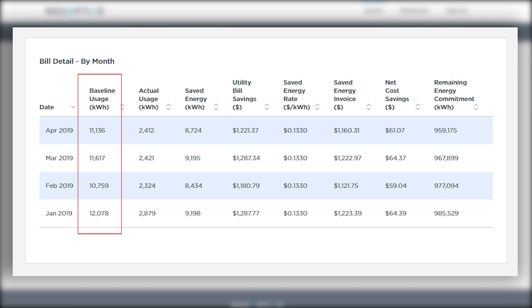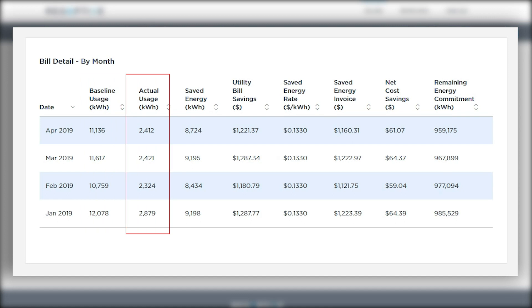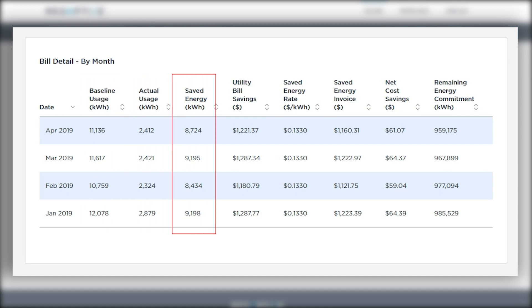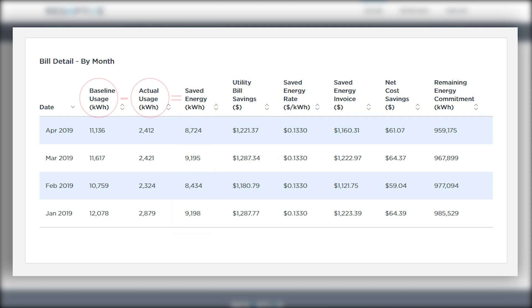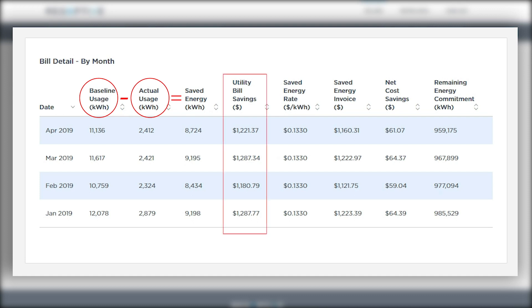Baseline usage in kilowatt hours is the pre-retrofit expected usage for this month. Actual usage is post-retrofit usage this month. Saved energy is this month's saved or avoided energy due to the retrofit, and we calculate this by taking the baseline minus the actual usage. This is used to determine the utility bill savings using the local utility rate.